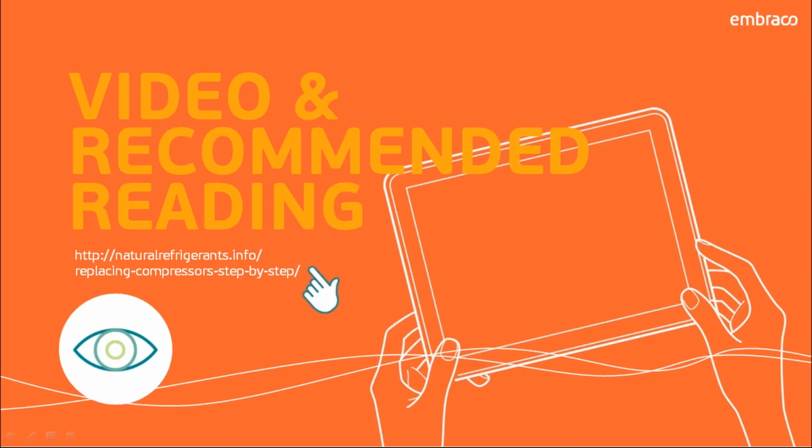Procedures for plugging in the equipment. Somebody's asking what that is. Basically, after you've followed all your procedures, it depends on what you're doing. If you're changing parts, if you left the cabinet doors open for a little while to vent the equipment, you changed your parts, and you've closed everything back up, you should be ready to plug that piece of equipment back in. Now, if I was doing service work, changing a compressor, or actually breaking into the refrigeration circuit, once I got everything repaired and reinstalled, I would definitely go over the system again and perform a final leak check, and make sure that the compressor and the unit are properly grounded. Then that unit should be perfectly ready to plug back in.